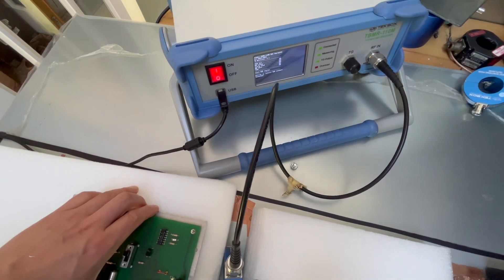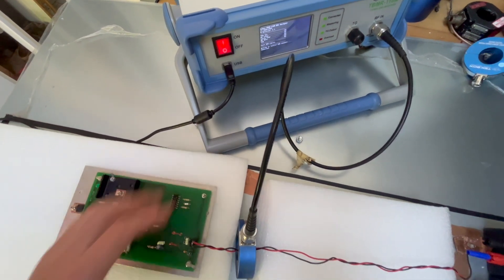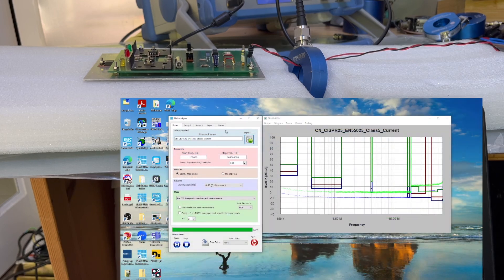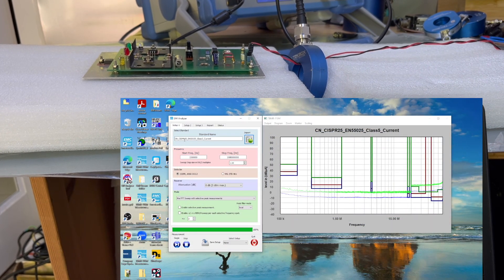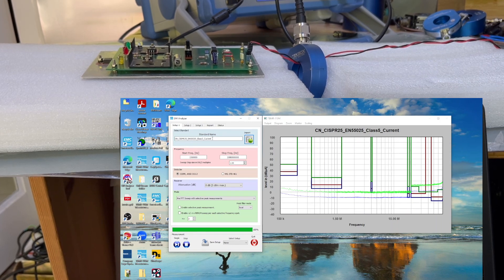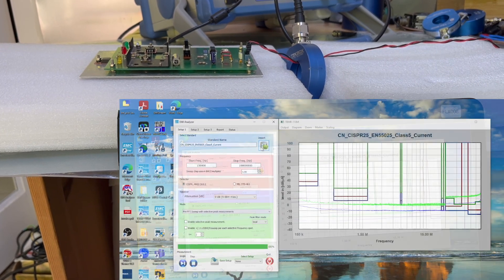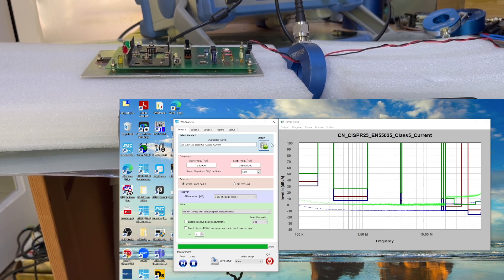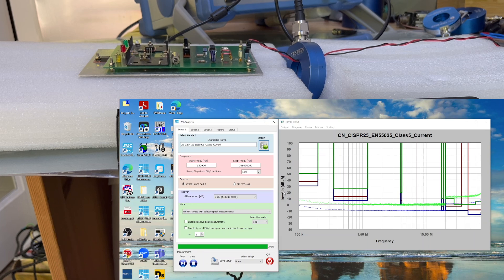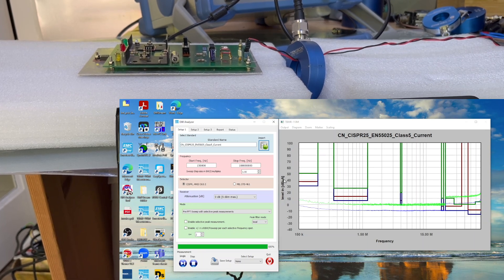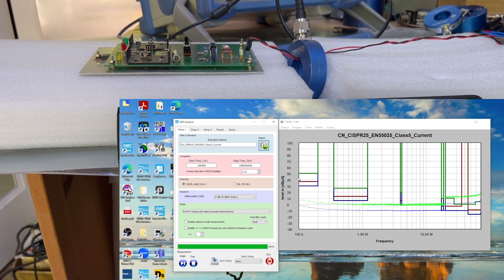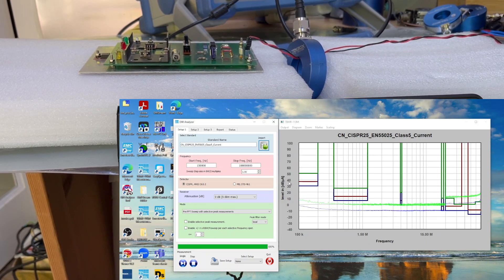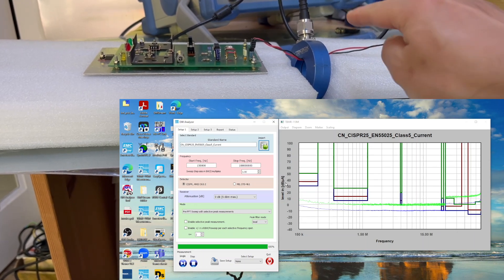We're going to use the Tekbox receiver for this demonstration. We open the software. As you can see, we selected the test method as CISPR25 current method. When we loaded the standard into the software, you can see on the y-axis it changes to dB microamps automatically.